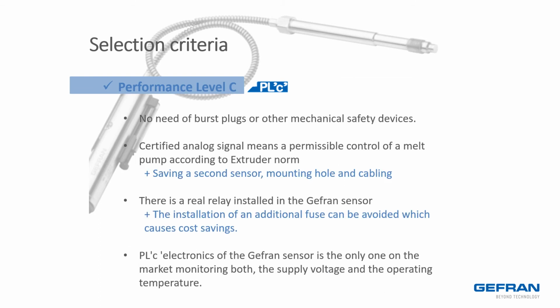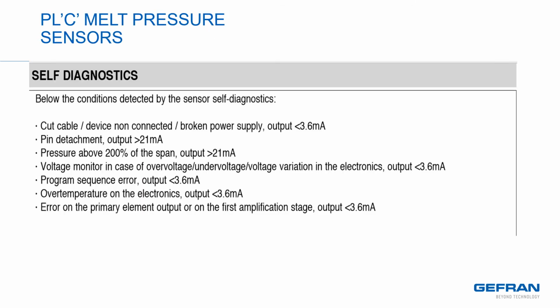A performance level C rated melt pressure sensor eliminates the need for a burst plug. The analog circuit is certified, making it preferable in the control of equipment like melt pumps. The sensor will be capable of self-diagnosis, as illustrated here. The information is available as a variation in that certified analog output.